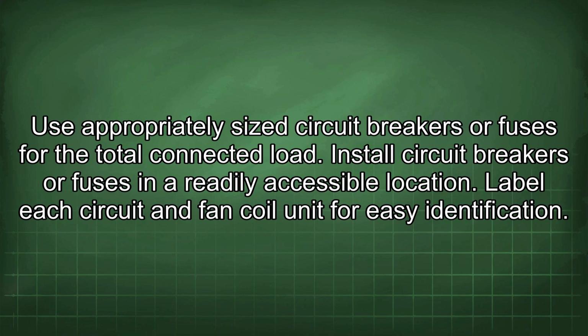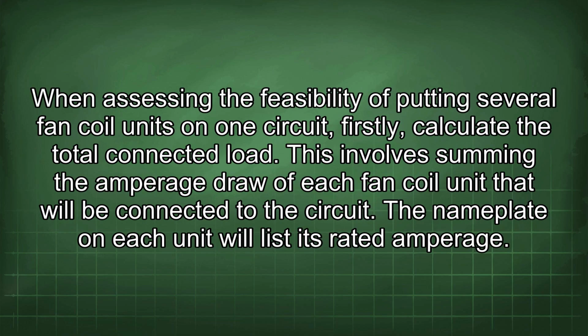Use appropriately sized circuit breakers or fuses for the total connected load. Install circuit breakers or fuses in a readily accessible location. Label each circuit and fan coil unit for easy identification. When assessing the feasibility of putting several fan coil units on one circuit, firstly calculate the total connected load. This involves summing the amperage draw of each fan coil unit that will be connected to the circuit. The nameplate on each unit will list its rated amperage.